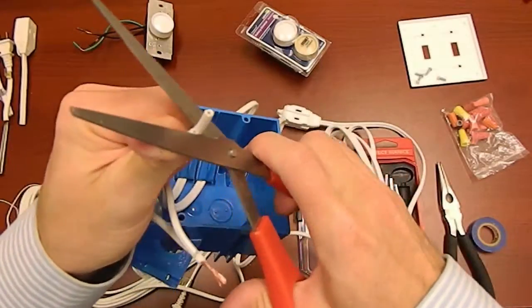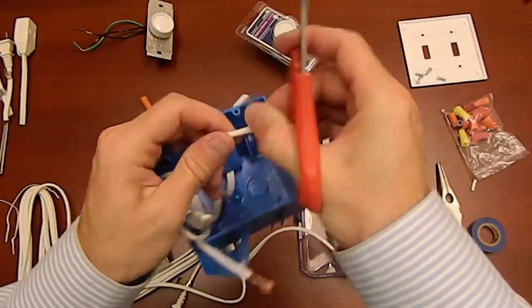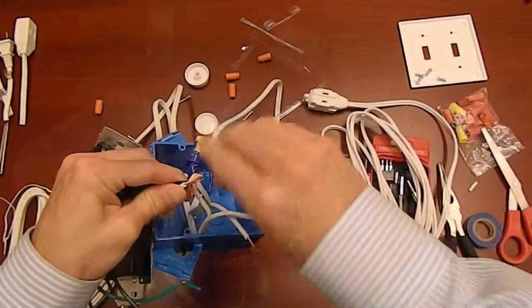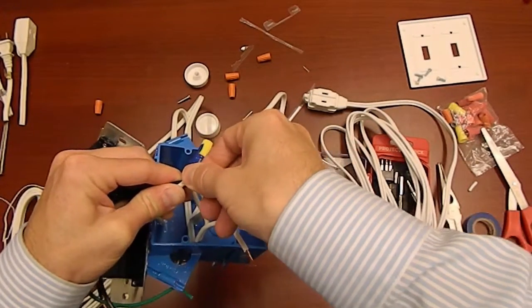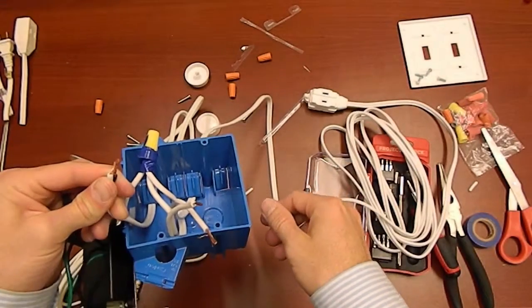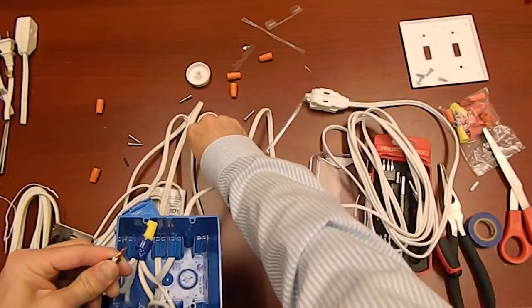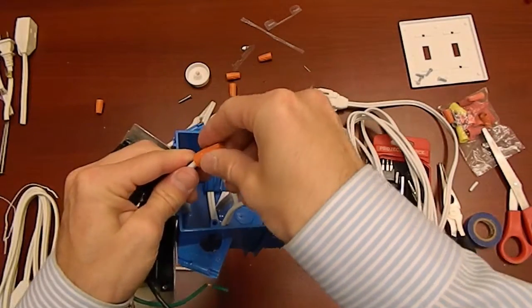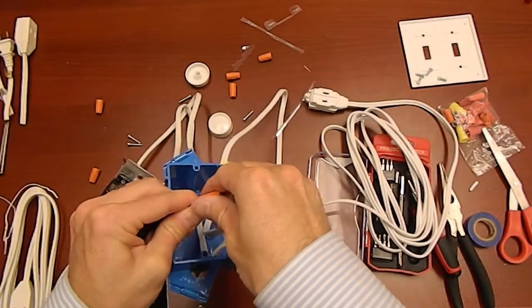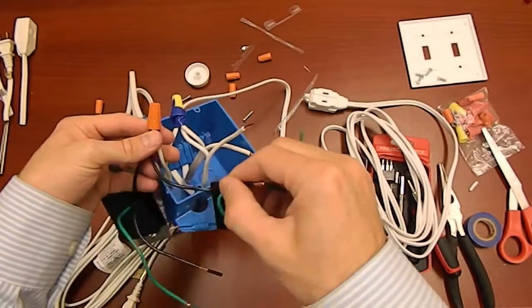And now I'm finishing up the hot wires. Now I'm joining up my incoming hot wire to one of the black wires from each dimmer. The power will come in and then split off to each dimmer switch. So I just join them all together right here. Then I'll secure them with a wire nut and then tape it down.